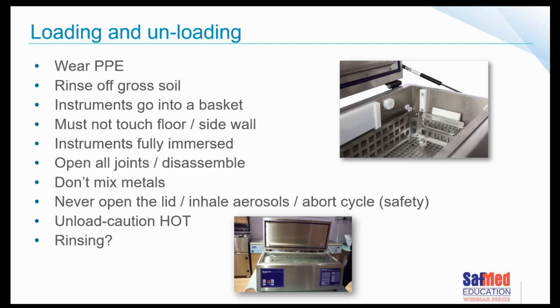As normal, you would open all the joints and disassemble everything that can be disassembled. If there are small items that you're worried about, there are little devices and attachments with small baskets that you can buy, to put the smaller items into, because you don't want screws falling off and landing up in the drain or anything weird or wonderful. Again, instructions for use: some laparoscopic instrument manufacturers may say that certain of the instruments can't go in there because it's not good for the joints, but you must understand and know those instructions for use.